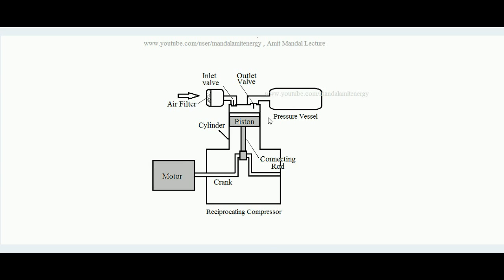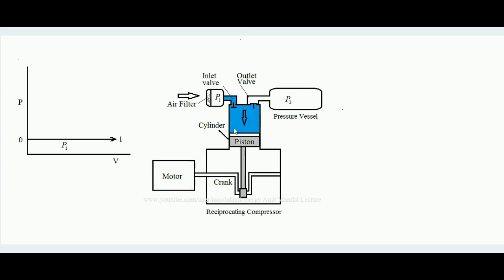Now let's understand its working. The reciprocating compressor has two strokes: suction and compression. Suppose the piston is at the top dead center and moves downward toward the bottom dead center — the inside pressure drops, so the inlet valve rises up from its seat and opens inward. Since it is a non-return valve, it opens automatically when the inside pressure goes low, allowing the piston to pull air in from the atmosphere through the air filter.